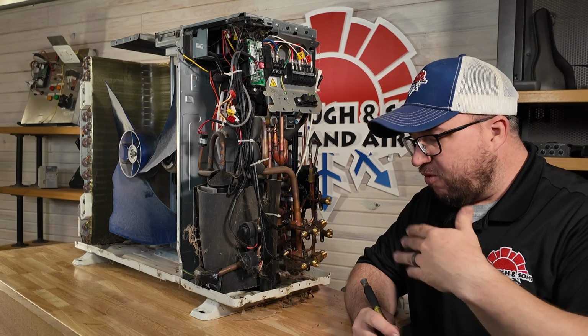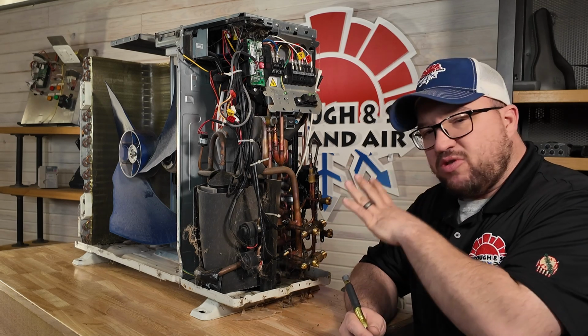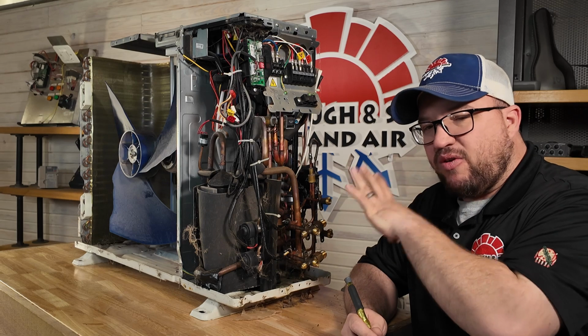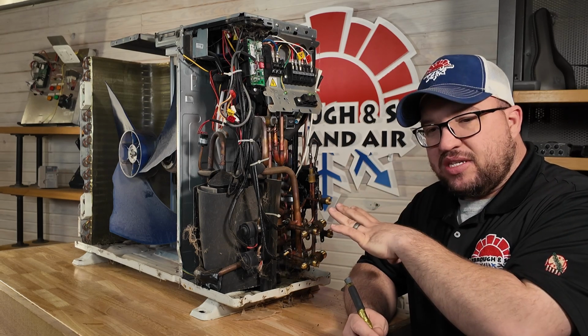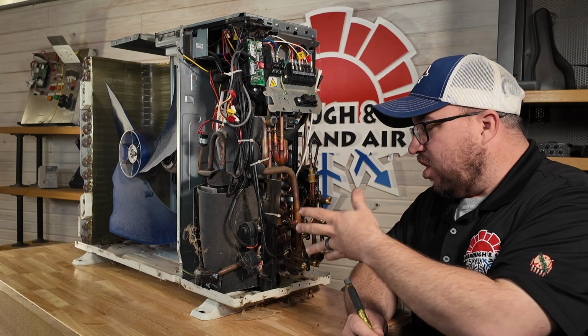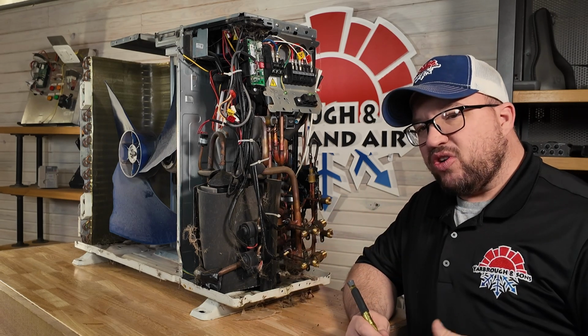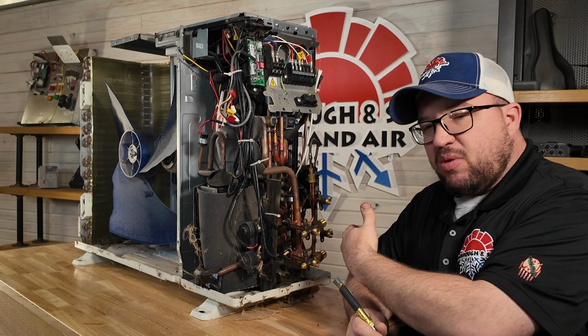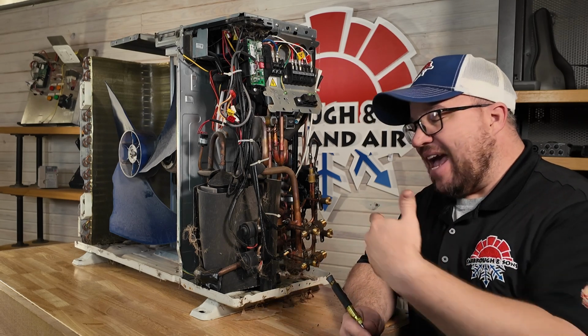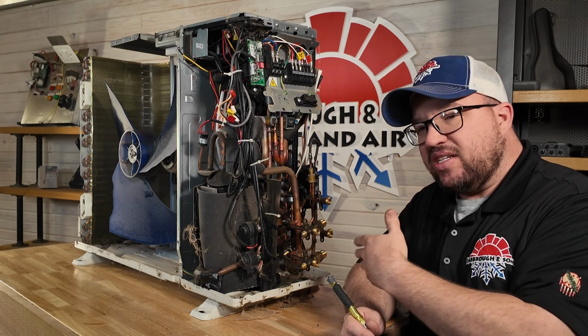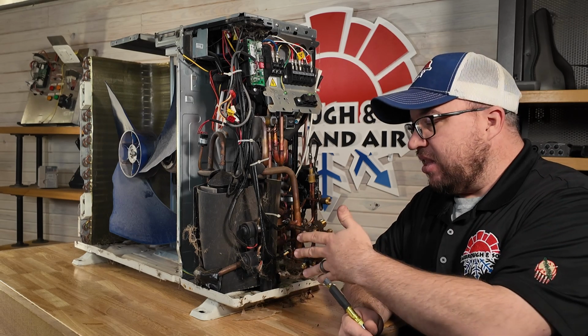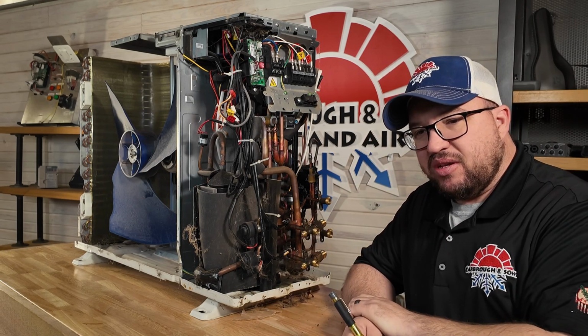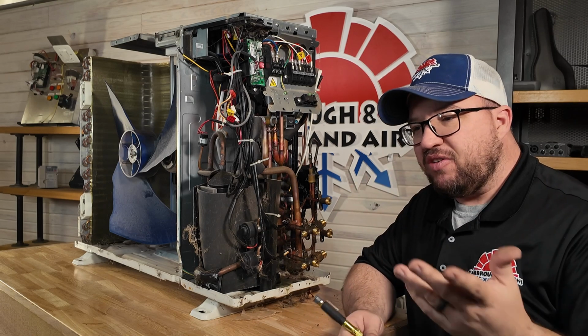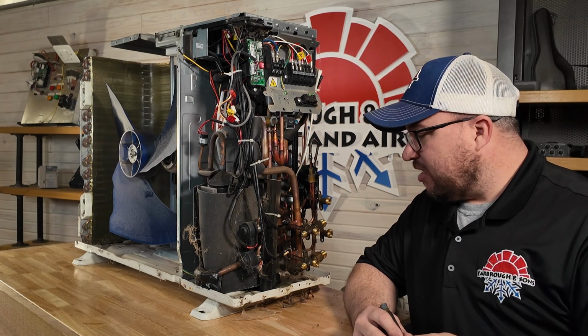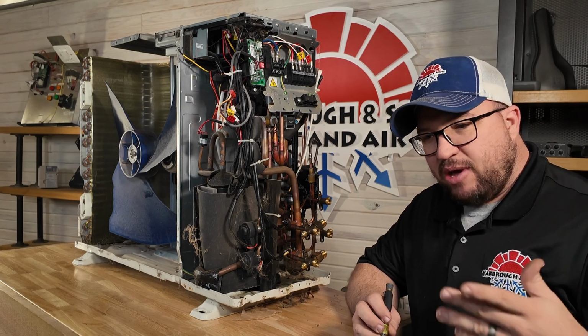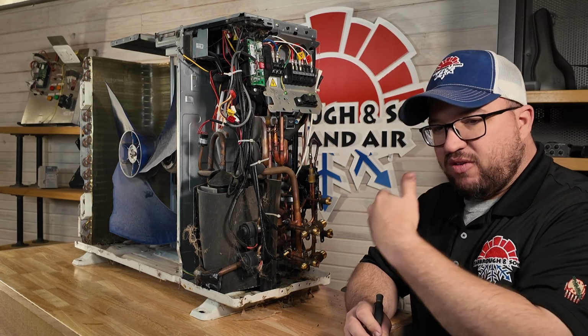Most of us that have worked on these for a long time understand these are critical charge units. We need to make sure that it has the correct charge. Otherwise, you can damage this system. So anytime that we want to work on a system and we think it's low on charge or overcharged, we're really supposed to pull all the refrigerant out and add back, weighing in the critical charge based off of the length of the line set and how much the unit is made for. So just simple little calculations. You can find it in any kind of install manual for these. That's one thing most service techs will complain about, but I find it's a lot better to know you have the correct charge.